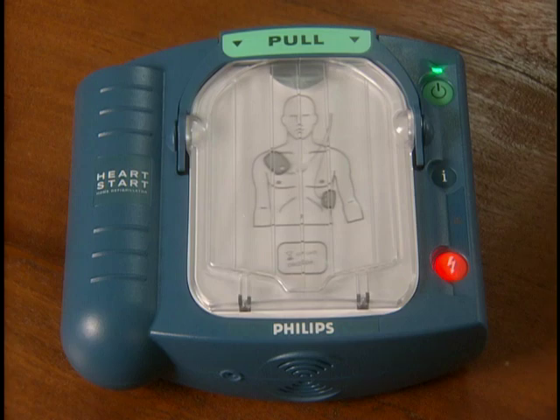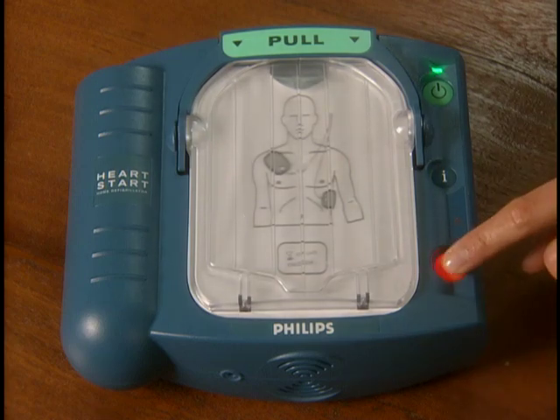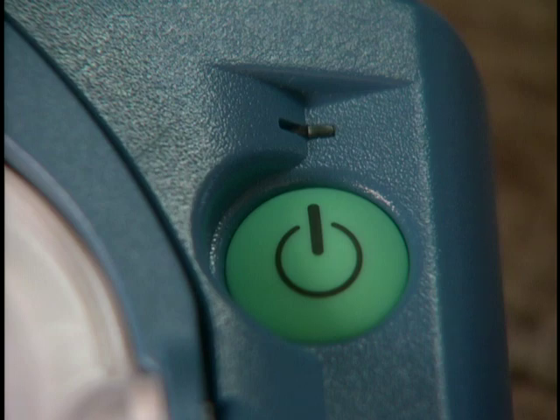As soon as the battery is inserted, the defibrillator will automatically begin a self-test, which takes about a minute. This is partly interactive, testing the various lights and controls. If the orange button is flashing, press it. Verified. The device will talk you through. Just press the buttons as instructed. After passing the self-test, it will automatically turn off and go to a standby mode, which means the defibrillator is ready for use as indicated by the blinking green ready light.